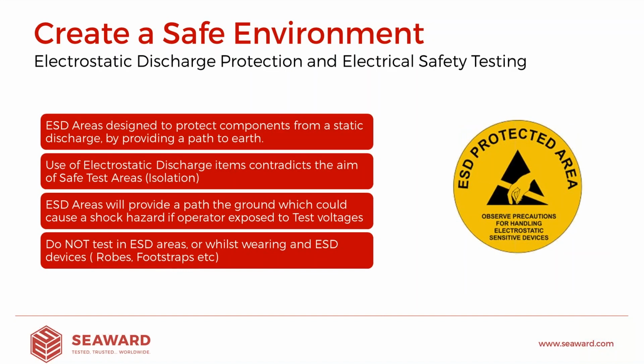I just wanted to, at this point, make a special note about ESD type areas. We're commonly asked about creating a safe working environment, and, oh, I don't need to comply with this because I have an ESD area. It's commonly mistaken that ESD is all about safety. Well, that's not necessarily so true. It's generally there to protect the equipment from a static discharge. And by doing that, with any kind of ESD, whether it's flooring, tabletop matting, clothing, or foot straps, we're effectively creating a path to ground. So you can already see from what I spoke about before, we don't want a path to ground. ESD is all there to create that path to ground.